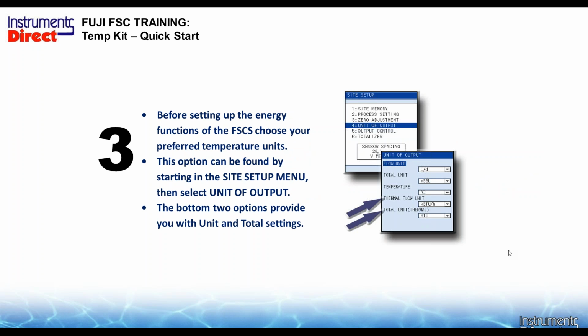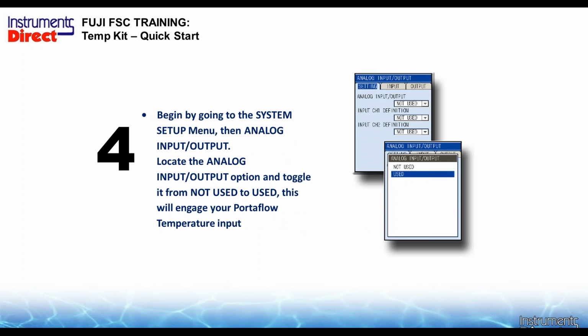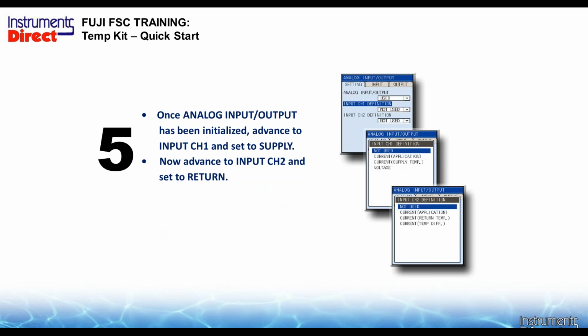So before you set up the energy functions with the FSCS, you need to choose your preferred temperature units. And this can be found on the site setup menu. Then select unit of output. The bottom two options provide your unit and total settings. Begin by going to the system setup menu and then select analog input output. Now, this is where you're doing temperature here, and this doesn't have to be temperature. We have people that put their pressure sensors in here as well. It's a fancy, fancy data logger with an analog input. You can use it for anything you want. In this case there, we're going to locate the analog port input and output option and toggle it from not used to use, and this engages the Portaflow temperature input.